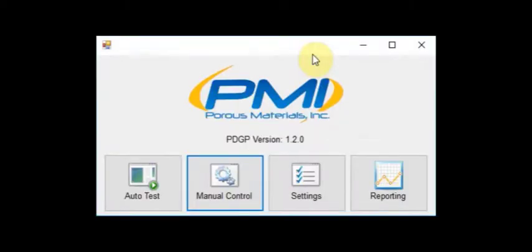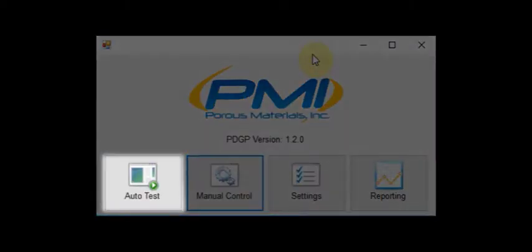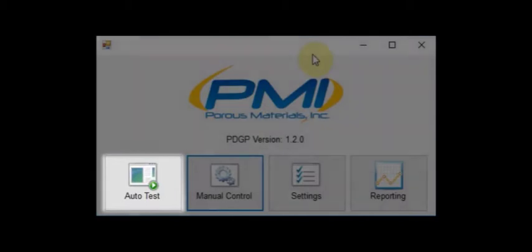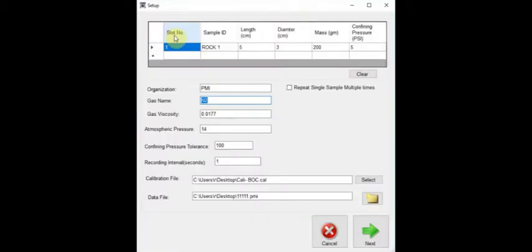Next, we will take a look at the auto test portion of the software. In the auto test setup window we can see several fields to input preferences. The table at the top of the window allows us to label a specific core sample with a slot number, sample ID, length, diameter, mass, and confining pressure. We also have the option to clear the table or repeat a single sample multiple times.